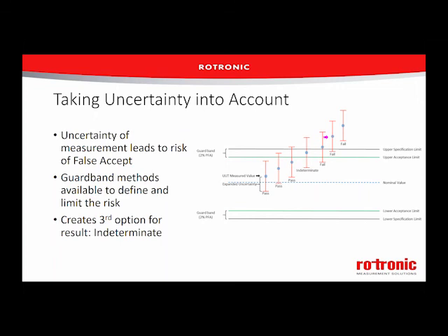So you're probably going to start to see these on more and more calibration certificates. You won't see indeterminate unless you've got a value that's crossing this guard band level. But especially once the new ISO 17025 comes out later this year, more and more labs are going to start to report the values in this format. So it's just something for you to understand, and hopefully not to be too surprised by when it comes out.